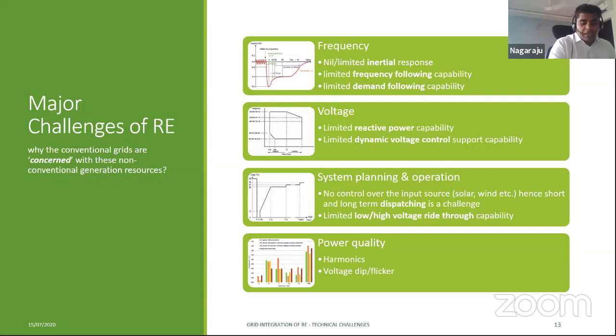And previously, the conventional machines have been able to ride through that and keep connected to the grid without tripping. What happens if, during a fault, generators keep on tripping under low voltage? You will lose further generation and the voltage will dip further, and we may end up losing the grid entirely. But the conventional generators have been helping us to maintain that. This is not the same with renewable energy. We will see that. The other aspect is power quality.